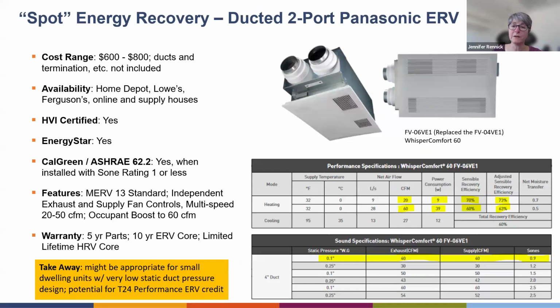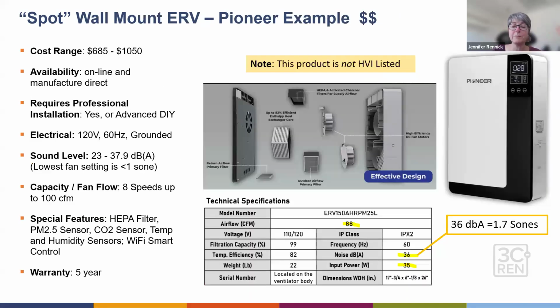Then you go up from there, and you're into those Panasonic two-port ducted ERVs. The efficiencies, we're wondering about that. Depending on the airflow, your sensible recovery efficiency is going to be anywhere from 60% to 70%. So it qualifies for Energy Star. And this can be appropriate for small dwellings with low static duct pressure design. This type, through the wall, on some of its speeds, it's not that quiet. It's 36 decibels, so 1.7 sones. It's just a little bit out of the Title 24 range for meeting the HVI certification and all that, but this could be really helpful if you want something that's easily installed with a HEPA filter and the PM 2.5 sensor, etc.